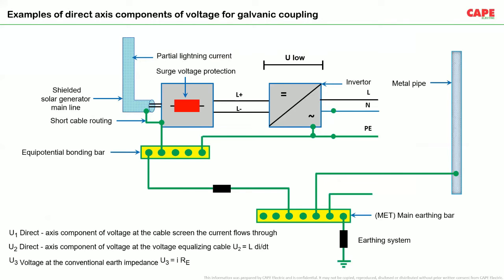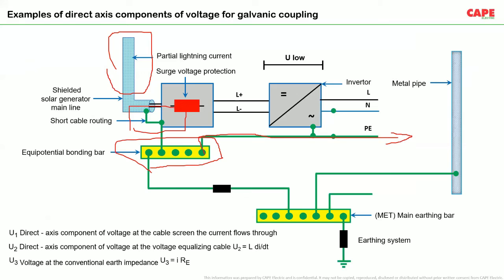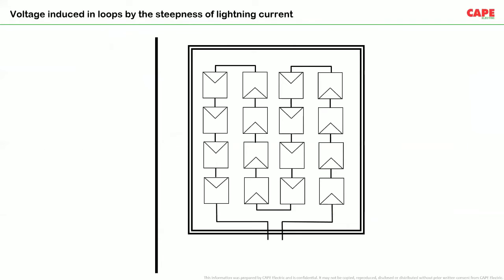Now, earthing. In one of the pictures, you can see the shielded wire is coming. The shielding is connected to the combiner box. In the combiner box, you see there is a small bus bar made, and the protective conductor is connected to the inverter, and the protective conductor goes towards the AC incoming. In the case of a TN-C-S system, it goes to the neutral of the transformer. In the case of a TT, it goes to the earth electrode. So this is how earthing has to be made. Of course, as I said, separate earthing of DC and separate earthing of the neutral of the inverter are illegal. Please don't do it.